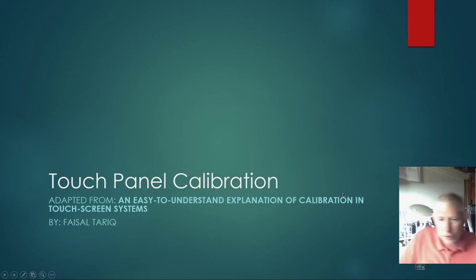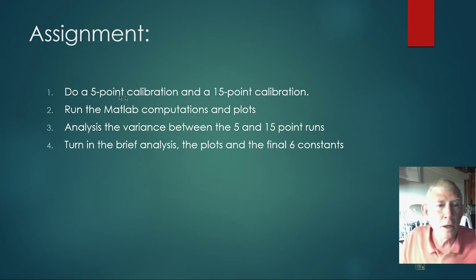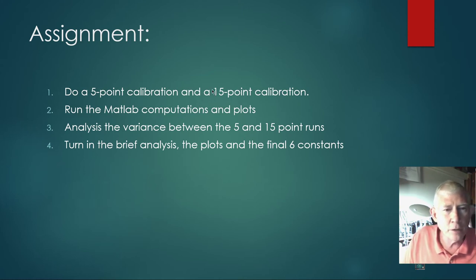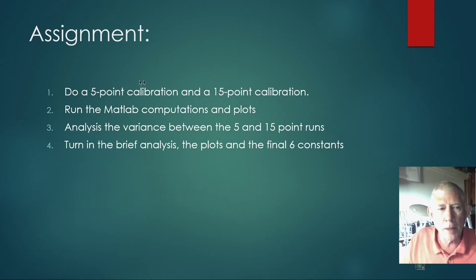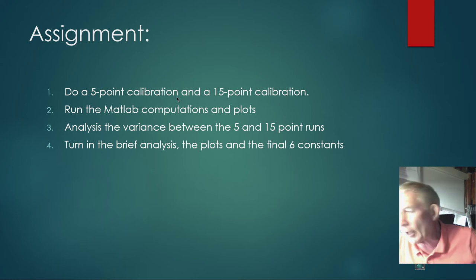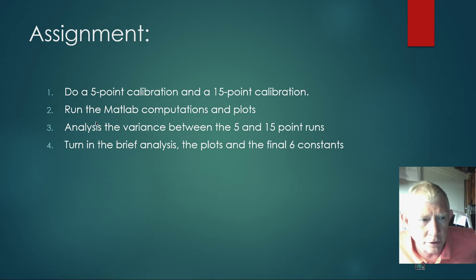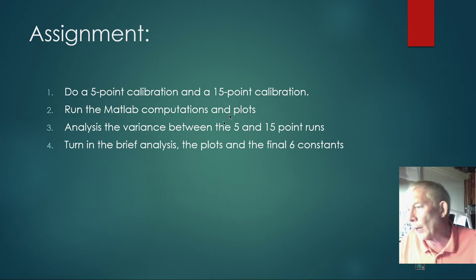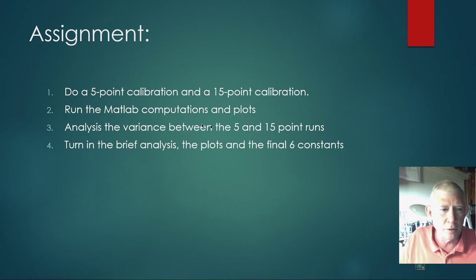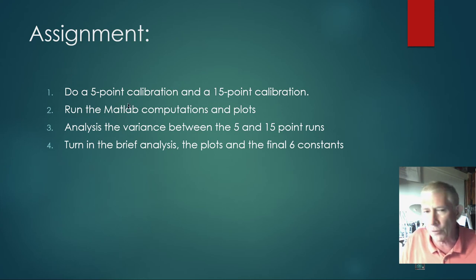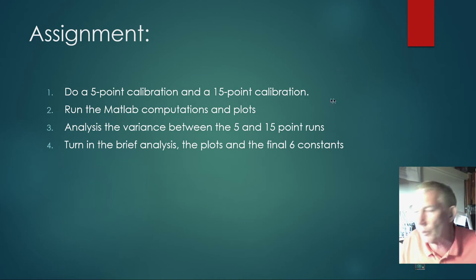I've been through the calibration. Do the five-point calibration first, then consider doing a 9-point or 15-point calibration for grins, rerun your MATLAB computations, and see the difference. You want precision more around the center than at far points. You can also adjust your linear coefficients F3 and G3 to place your center point right on the center.